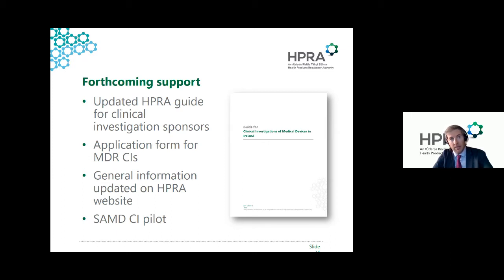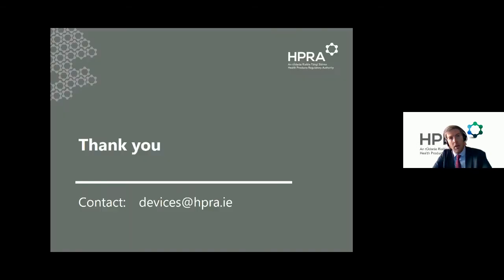For forthcoming supports primarily related to MDR implementation in the new year: we're working on updating our guide for clinical investigations for sponsors, developing the application form for clinical investigations under MDR, and providing lots of general information on the HPRA website starting in Q1 of next year. We're also working on a pilot scheme for clinical investigations of early phase and low-risk software-based medical devices, to help facilitate those types of studies where considerations from a safety, performance, and regulatory perspective can be quite different — to try to expedite assessments of those products.